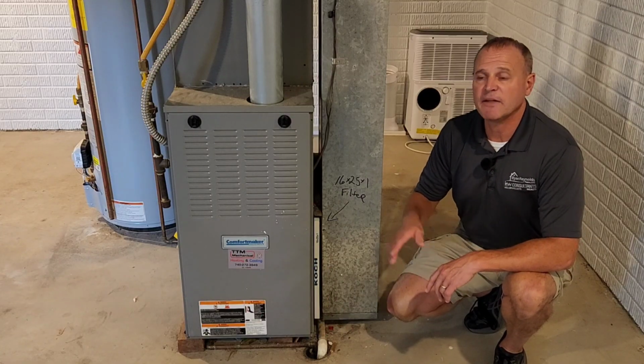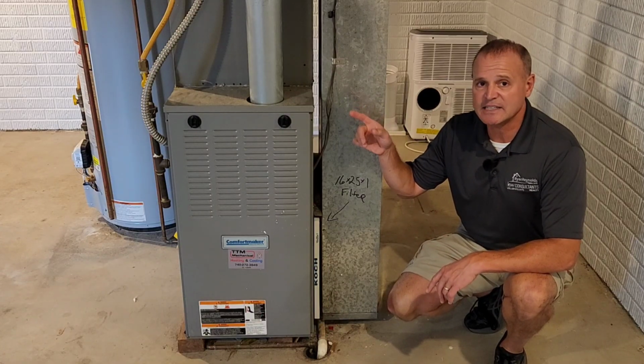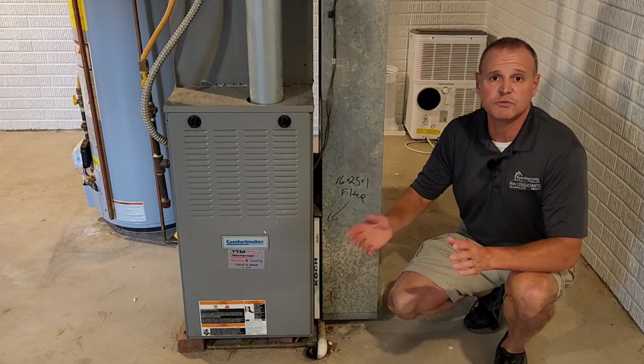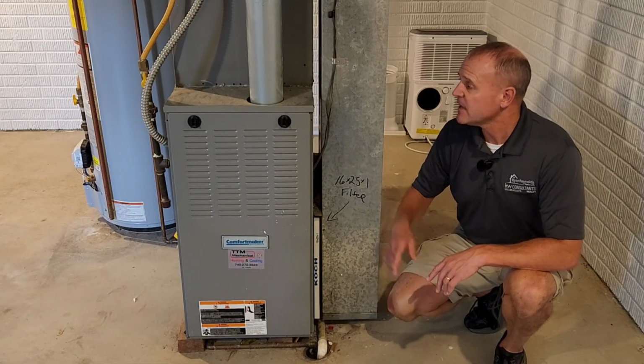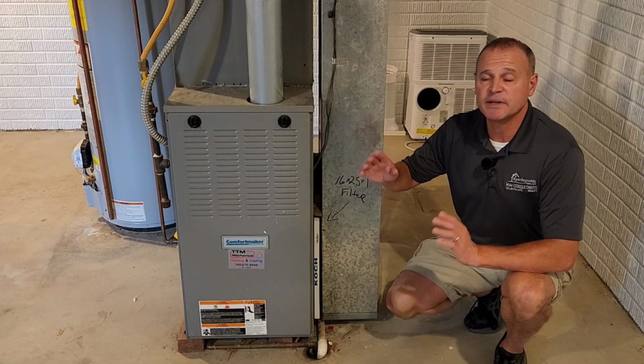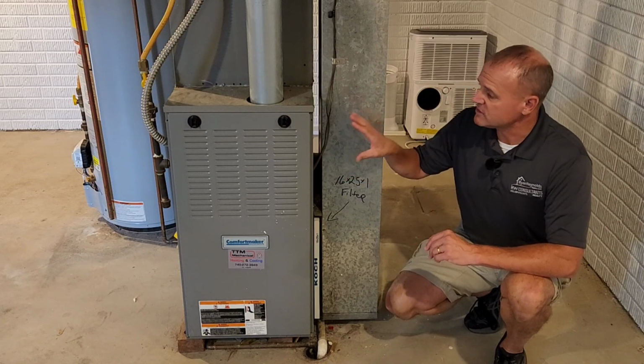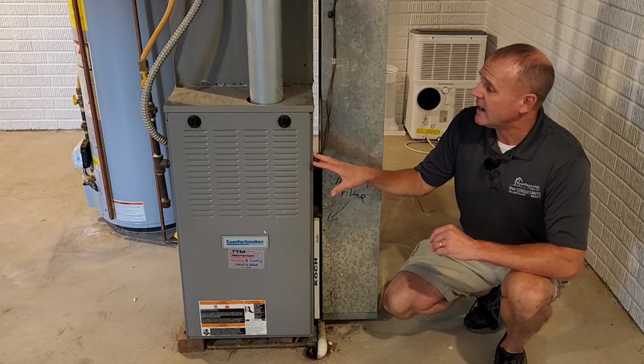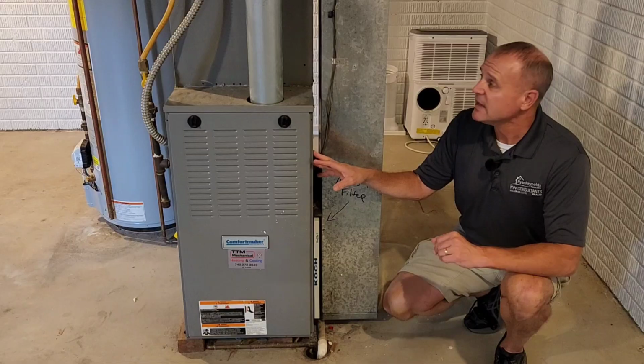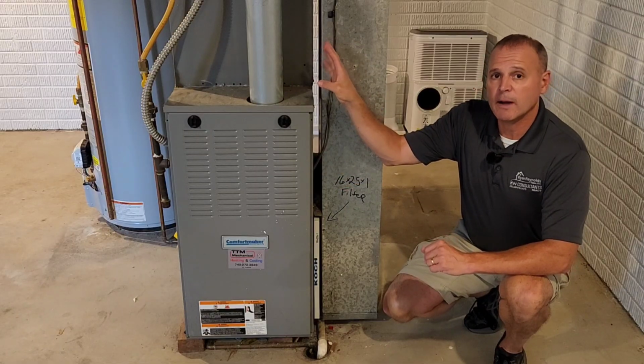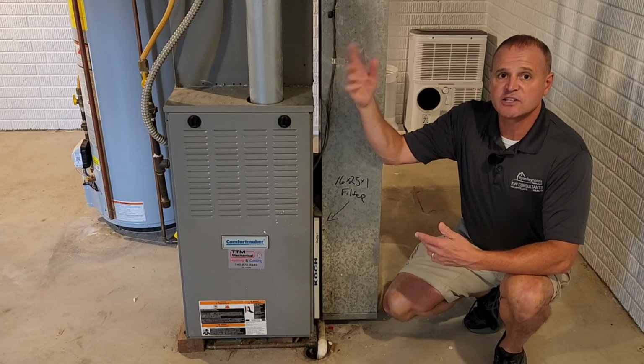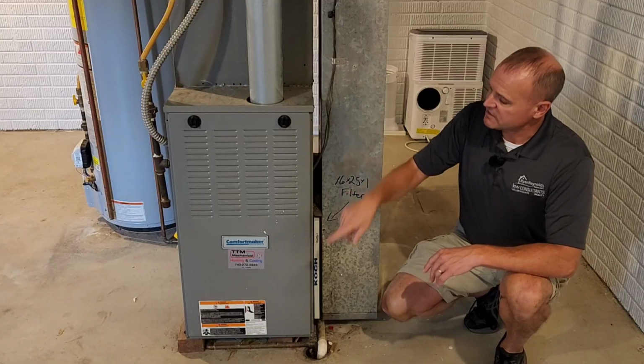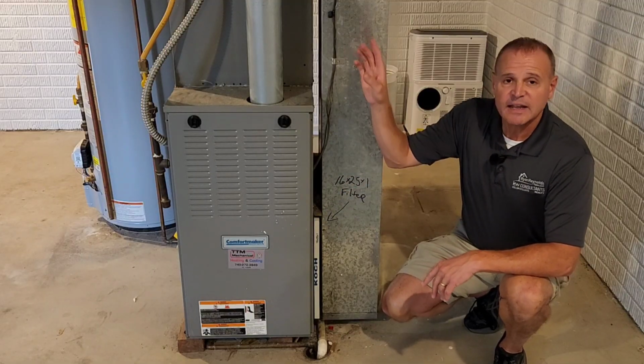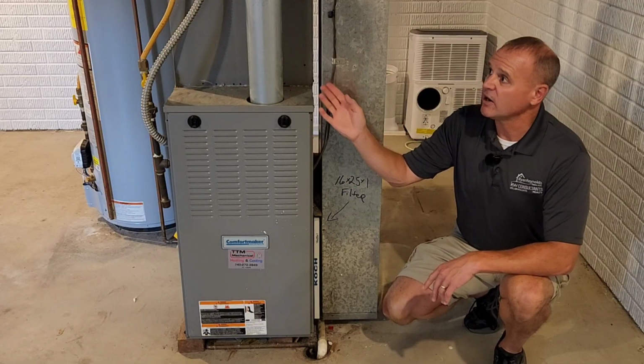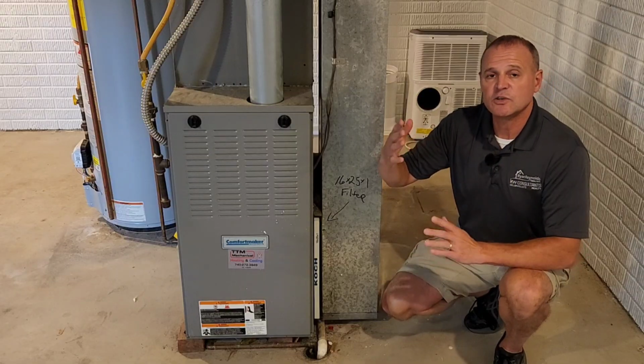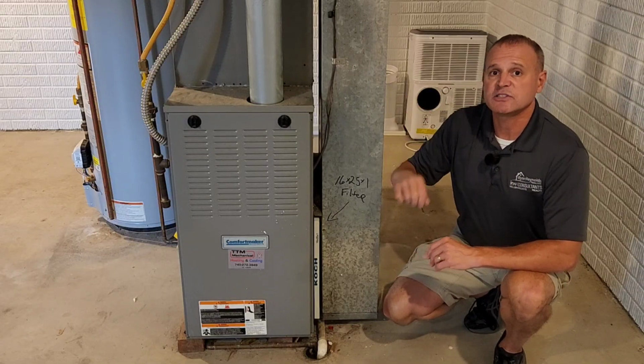So today we're talking about the drain line coming from your air conditioning condensate to the actual drain in the floor, or to potentially a pump in some cases. It's important to keep that drain line open because of the way a furnace is built. You essentially have your furnace part down here along with your air handler, which is the fan, and you have your A coil up here, which is where the cooling lines go to cool the air. The fan down here blows air up across the A coil, through the cooling lines and fins, and that gets distributed through your house with the ductwork.